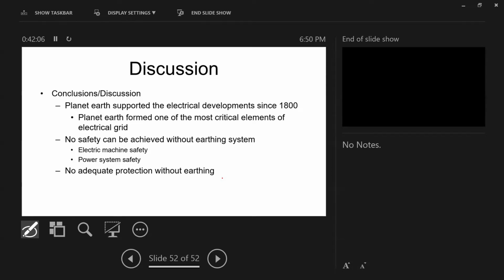Without an adequate earthing system, without studying the Earth, let me tell you guys, I spoke to one of my colleagues here in the industry earlier this year. They want to do a substation, but they cannot choose a site because it's a DC line, because of the electrodes. You have to have a proper earthing system. In many places, we have to relocate our substations because the cost of the earthing system is massive. Without an earthing system, we cannot maintain safety.